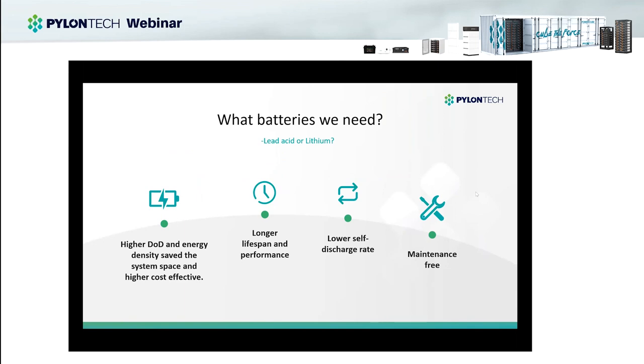Now we need to design the system. Considering the equipment, especially batteries, which represent a high percentage of total system cost — lithium is the new standard in larger off-grid systems because of its reliable performance at high temperatures, optimal scalability, and fast discharge and charging abilities. From an investment perspective, a long cycle life translates into a lower cost per cycle compared to lead-acid batteries, and it is relatively maintenance-free. Lithium batteries are also lighter and more compact, ideal for installations with space or weight restrictions.